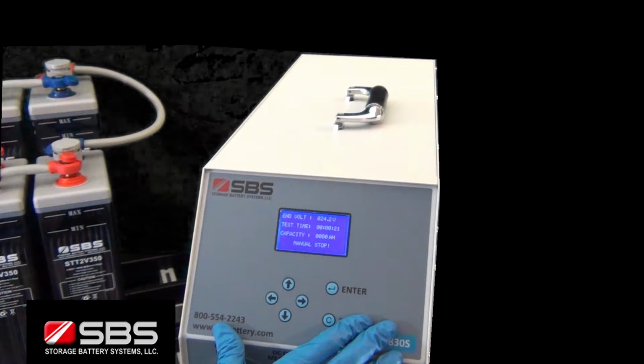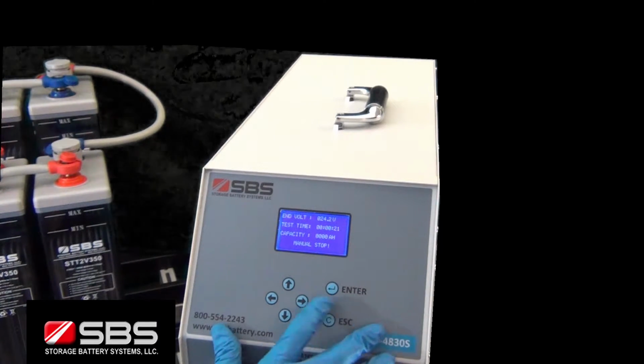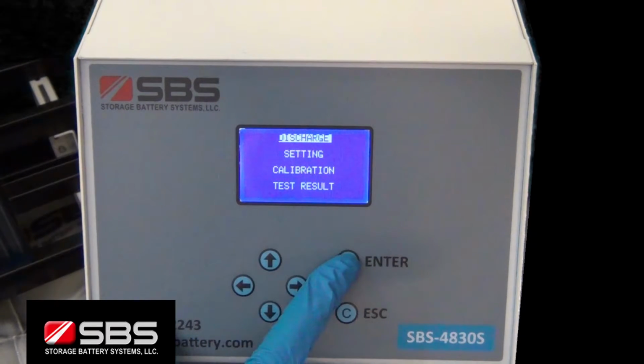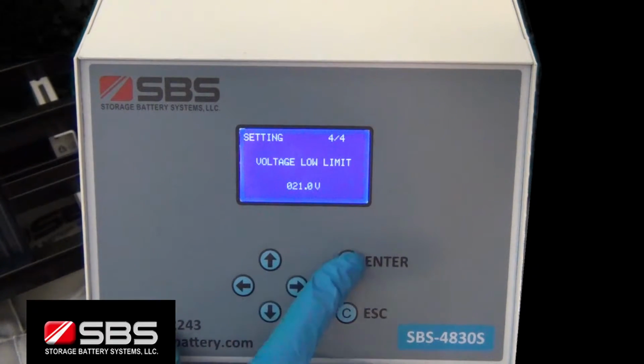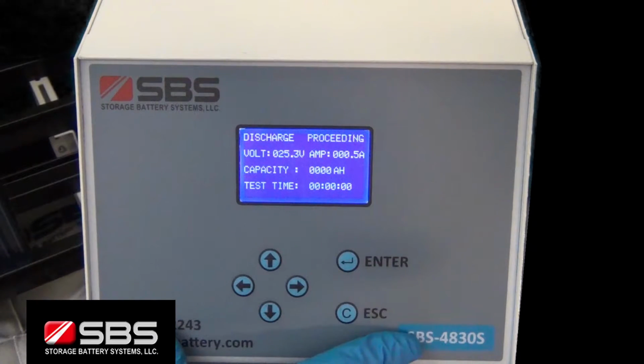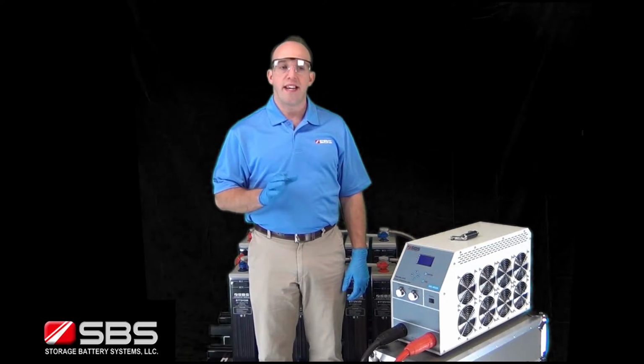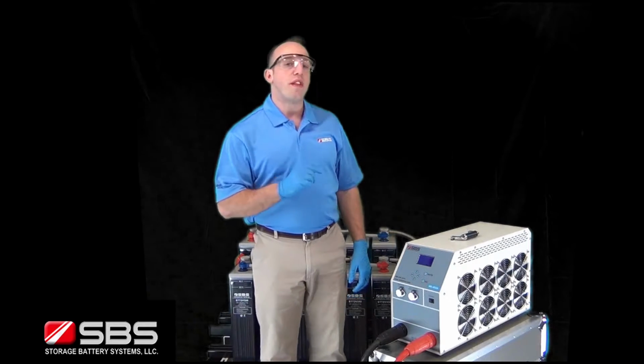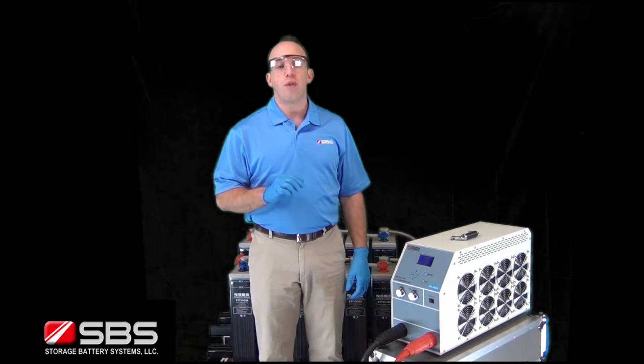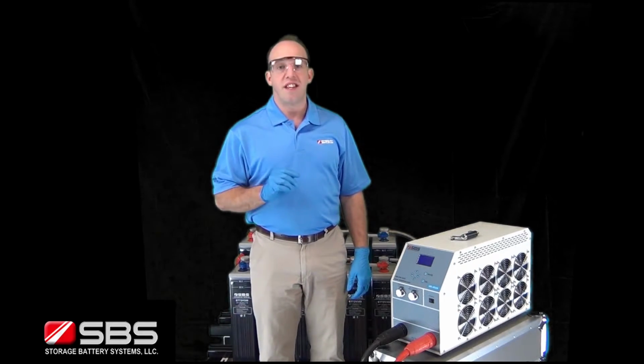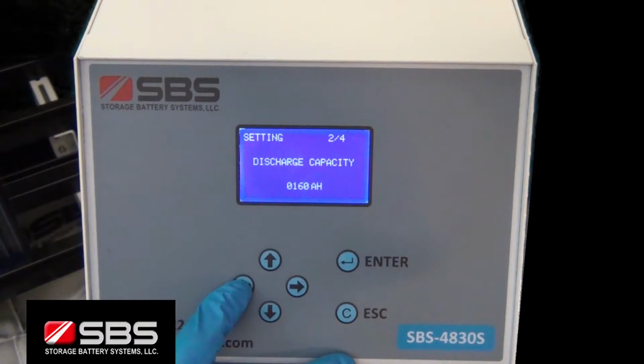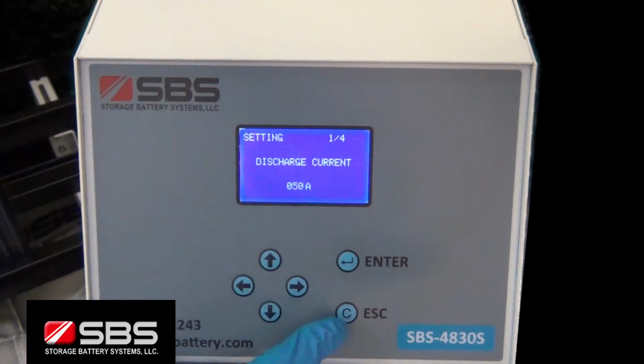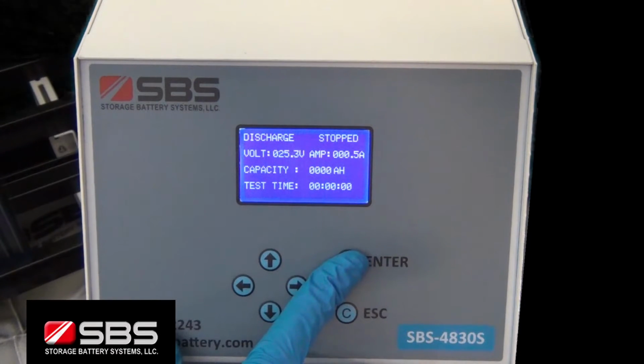Now that you have an understanding of the features of the SBS S-Series, we can begin our test. In the main menu, use the up and down arrow keys to select Discharge and then press enter. The SBS S-Series will display all of the test parameter settings before the discharge begins. Use the left and right arrow keys to verify all settings are correct and then press enter to start the discharge. You may modify the settings values during the test by pressing the right or the left arrows to go back to the parameter settings screens. From here, you can modify these values by using the up and down arrows and by pressing enter to activate the new setting and continue discharge testing.